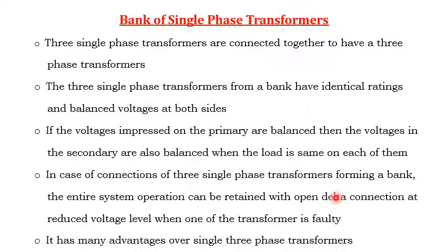The advantage of a bank of single phase transformers is that if any one of the transformers goes into a faulty condition, the entire system operation can be retained with the open delta connection, but it will operate at a reduced voltage level. It has many advantages over single unit three phase transformers, so we will study what those advantages are.